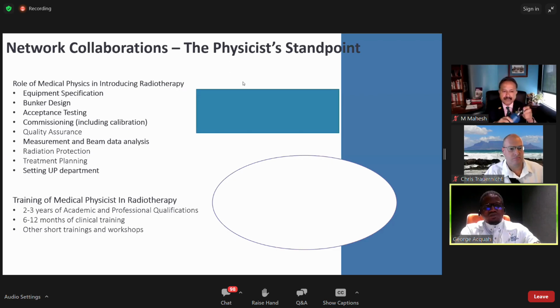So from the medical physics standpoint, when I'm talking about network collaboration, what do I really mean? It means that for a clinical medical physicist, your role, specifically when it comes to the introduction of radiotherapy in a facility or your country, has to do with equipment selection, which is very important. The design of your radiotherapy bunkers, acceptance tests when the machine is installed, and commissioning, which includes the calibration of the machine. Then from your commissioning, you come up with your quality assurance program, the measurement and analysis of your beam data, radiation protection, treatment planning, and setting up. So these are very key roles of a medical physicist when it comes to the setting up of radiotherapy.